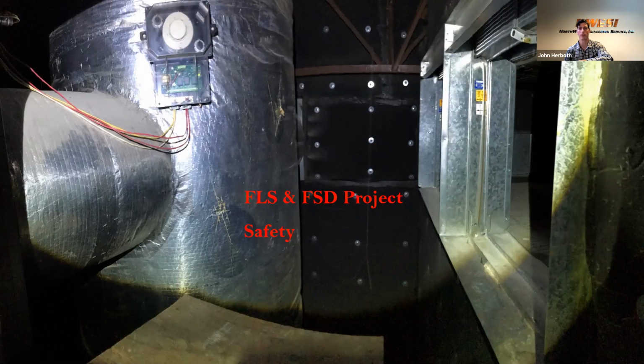Those requirements, if you are doing a certification, you do have to test every single aspect of it and every single failure type as a requirement, and not just say a sample that is part of your commissioning scope. So we verify everything that you're required to verify, and then what's typical for commissioning is, you do a sample, and you just can't do that if you're the one certifying it. So we'll test everything. I mean, you have to.